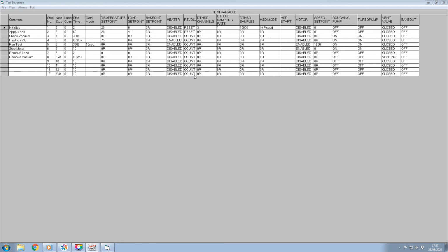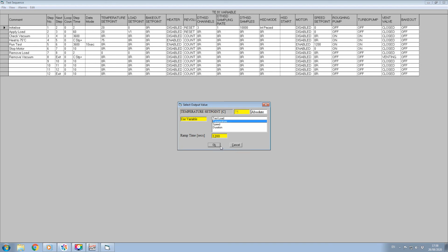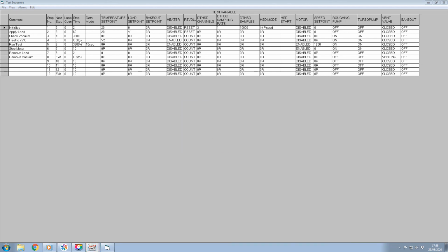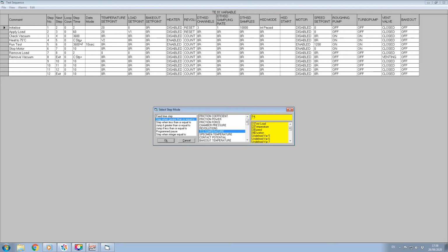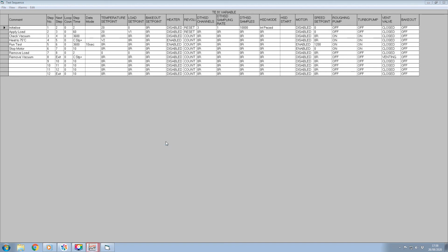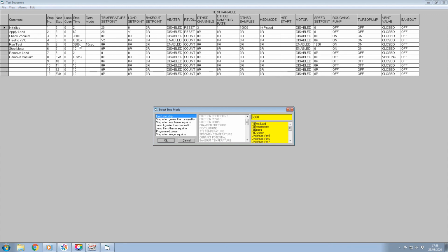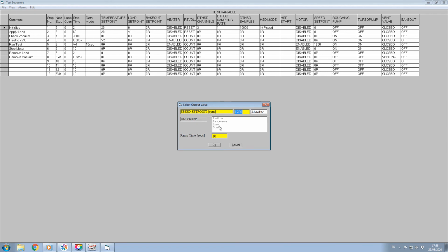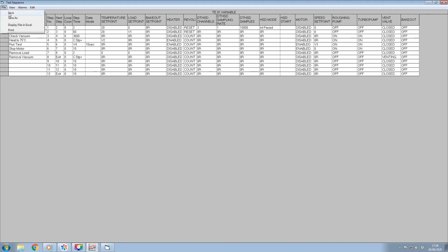We can now use the other variables as required, for example, V2 as the temperature set point for step 4. We can also use a variable for the value in a conditional step. So instead of using 80 degrees centigrade as shown here, we can choose variable V2 by selecting temperature from the list. Once we have defined all the required variables, we can save the test sequence file and run the test in the normal way.